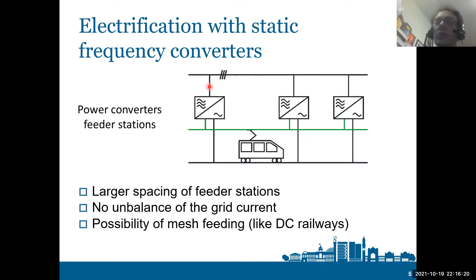Due to the controlled nature of the converter, we can avoid the neutral section because we can avoid the circulation of power between the traction substations, and then each train is fed by two or more substations, and that enables a larger spacing between the feeder stations. Similarly, the controlled nature of the converter enables us to draw balanced current from the grid, and therefore there is a possibility of connecting to a weaker grid or even to grids at lower voltage, thus saving on the connection costs.